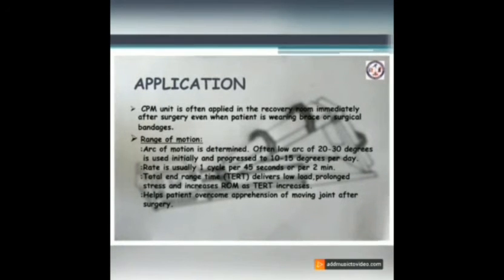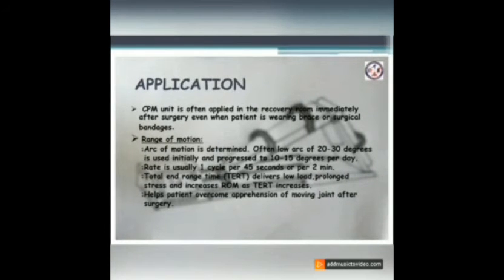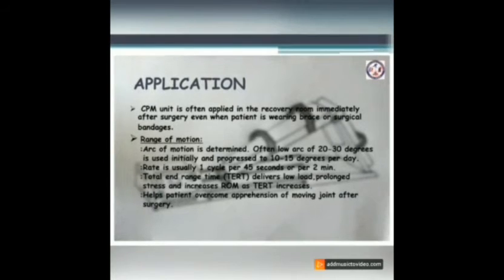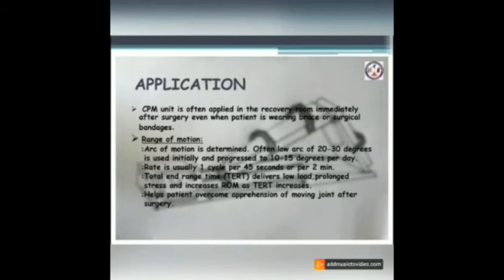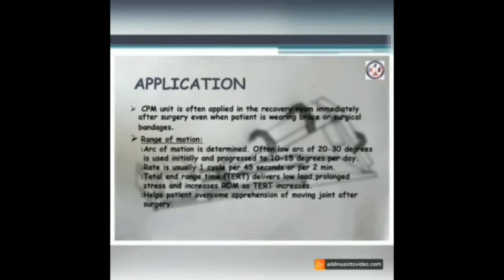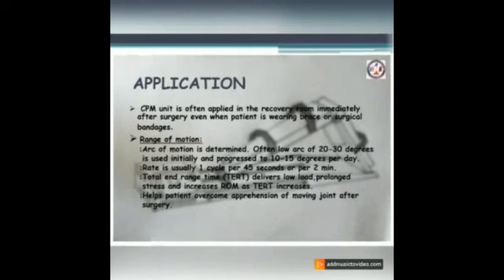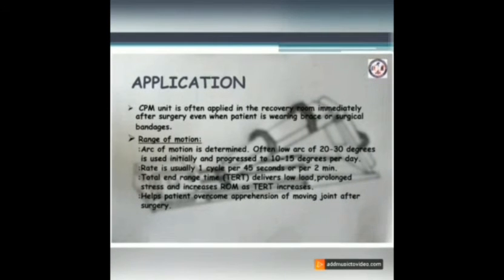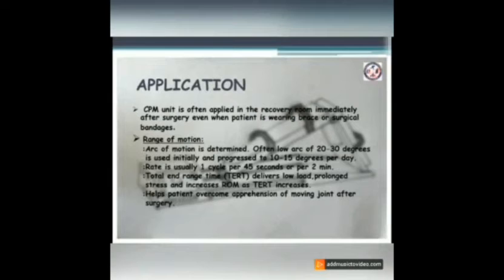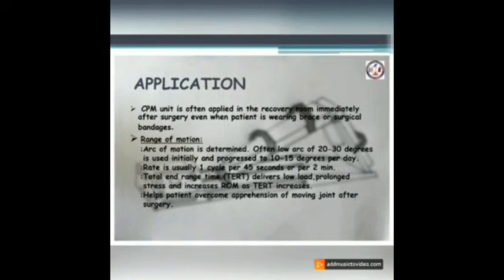Specifications: CPM units are often applied in the recovery room immediately after surgery, even when patients are wearing braces or surgical bandages. The arc of motion is typically 20 to 30 degrees initially, progressing 10 to 15 degrees per day. Rate is usually one cycle per 45 seconds or per two minutes.